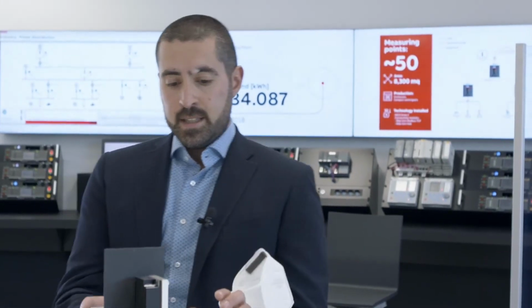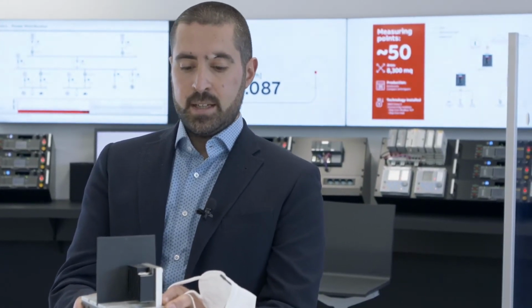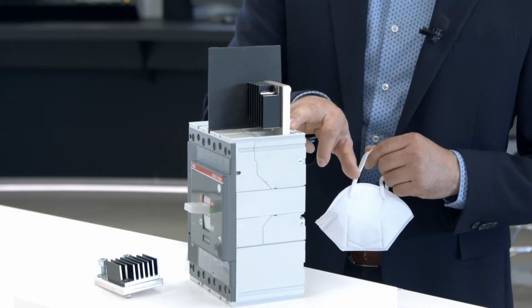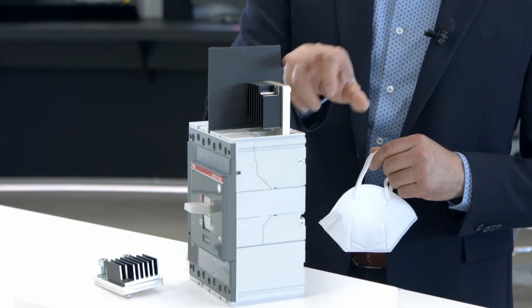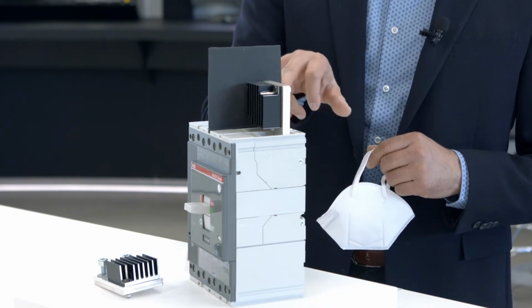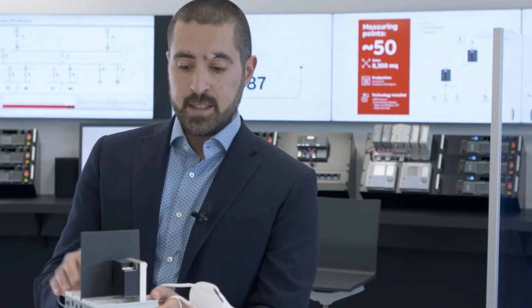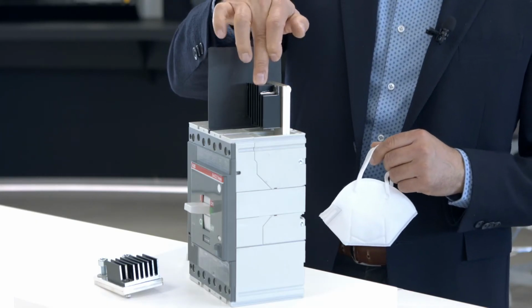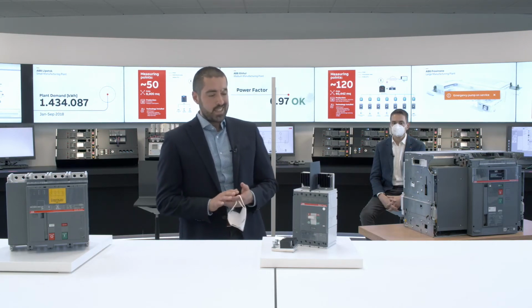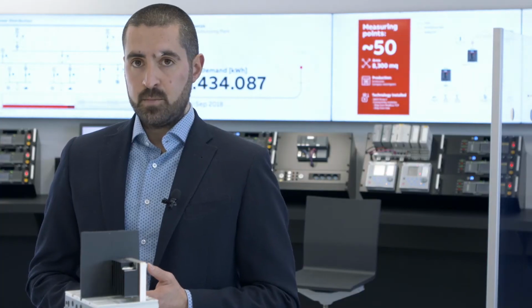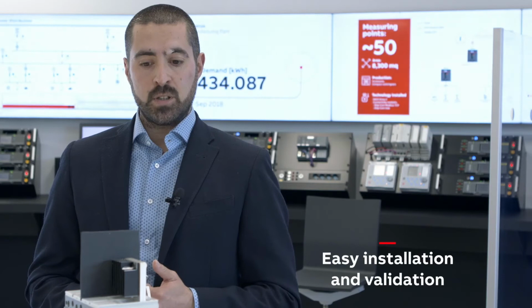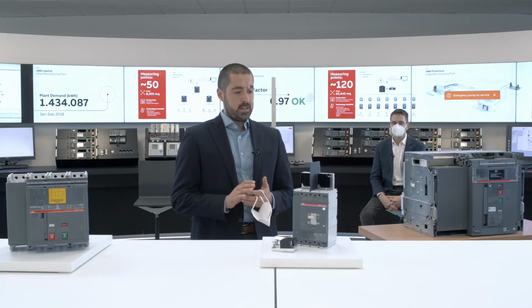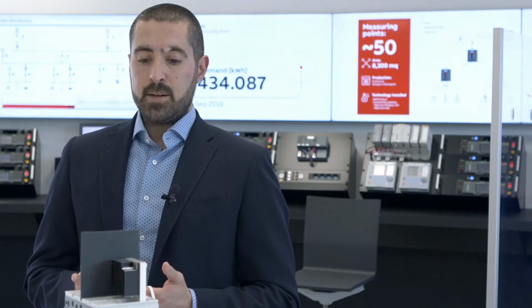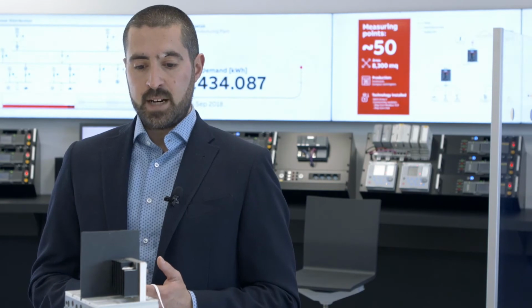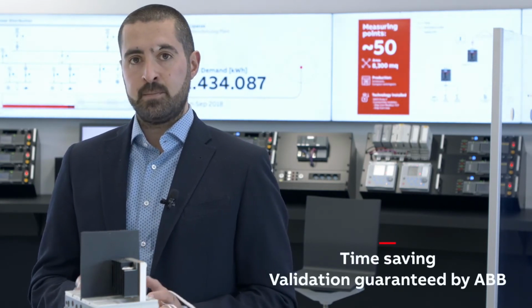For this reason, it is mandatory to mount jumpers because they are tailor-made on the terminal dimensions of the ABB devices, and with the mounting of jumpers plus the phase barrier, it is possible to reach the insulation between poles and also to manage in an easy way the temperature on the terminals thanks to the heat sinks mounted directly on the jumper. In all the other cases, jumpers are not mandatory, but as ABB, we strongly recommend to use jumpers. First of all, because they are a time-saving solution. And second, because all the tests in order to declare the technical features on ABB catalog are made with jumpers. So, with the use of jumpers, customers are sure to have a device with the performance declared by ABB on the catalog.